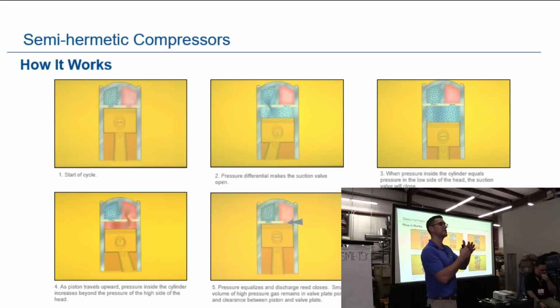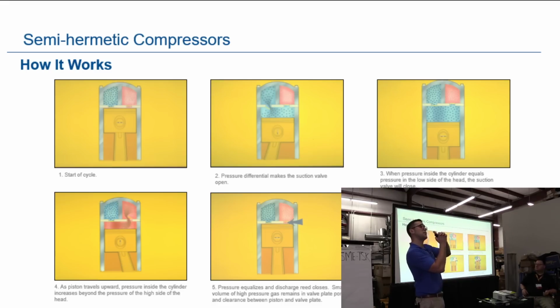Exactly. So as the compressor starts up, it pulls down. As the pressure starts to drop, it opens up, pulls it down, opens your suction, and then as it starts to go up, it starts to compress that refrigerant as it goes through the cycle, right? As it starts to compress, it closes the suction valve, and then opens the discharge and pushes it out. And it just continuously does that, continual compression. One thing I want to note, and you can see a little arrow right here, is something called the volumetric efficiency loss on our reed compressor.